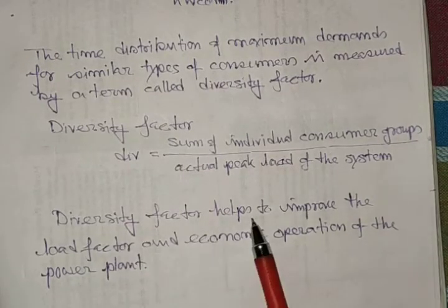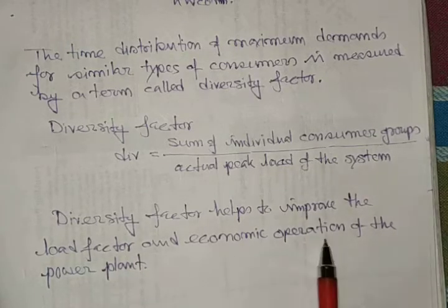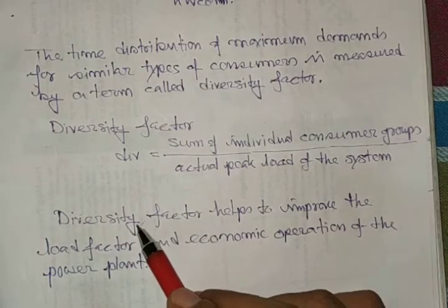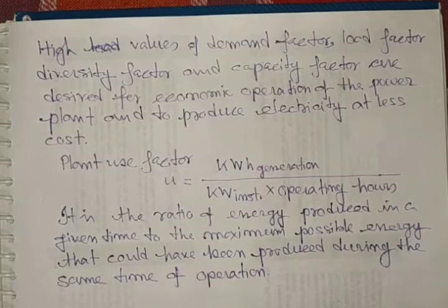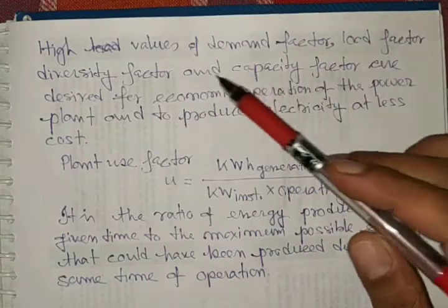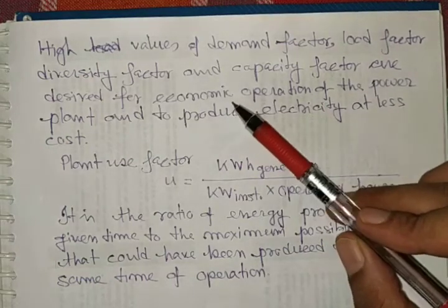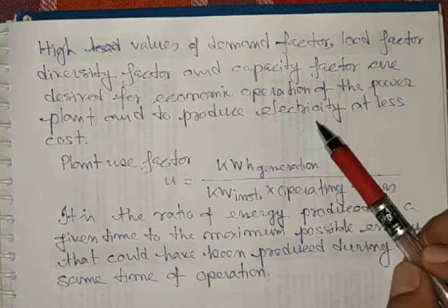Diversity factor helps to improve the load factor and economic operation of the power plant. So it is a very vital element of power plant engineering in terms of economy. High values of demand factor, load factor, diversity factor and capacity factor are desired for economic operation of the power plant and to produce electricity at less cost.